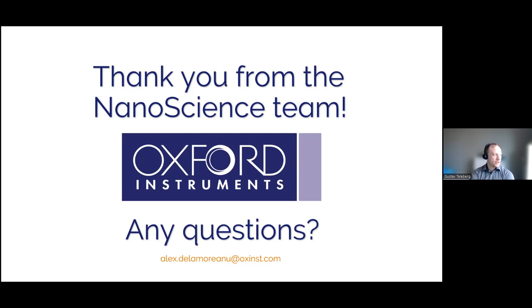So if the electronics is dissipating heat at 4 Kelvin primarily, then it basically boils down to the same problem as cooling down an FPGA, for example, which people generally install at 4 Kelvin. It boils down to pulse tube power, so that's not an issue. Some of our customers are playing around with high dissipative powers at millikelvin temperatures too, and the cooling power is certainly there for it. The rest of it is more about thermally anchoring wires and things like that.